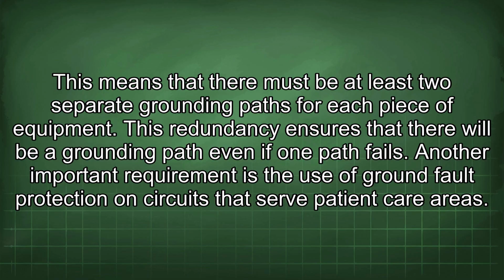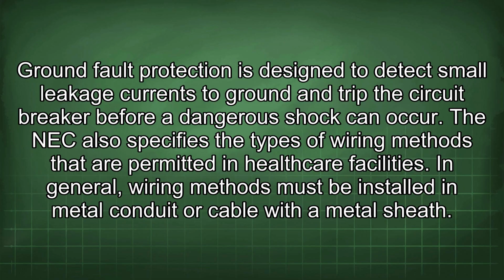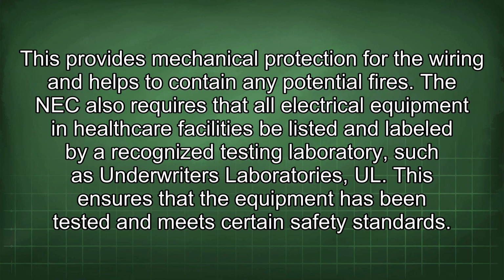Another important requirement is the use of ground fault protection on circuits that serve patient care areas. Ground fault protection is designed to detect small leakage currents to ground and trip the circuit breaker before a dangerous shock can occur. The NEC also specifies the types of wiring methods that are permitted in healthcare facilities. In general, wiring methods must be installed in metal conduit or cable with a metal sheath. This provides mechanical protection for the wiring and helps to contain any potential fires. The NEC also requires that all electrical equipment in healthcare facilities be listed and labeled by a recognized testing laboratory, such as Underwriters Laboratories. This ensures that the equipment has been tested and meets certain safety standards.